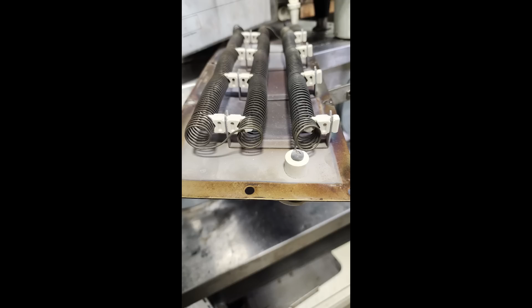This is the old heating element I took out, and over on the left you can see one of the terminals - the ceramic insulator is cracked on one side. This side you're seeing now is good; this little ceramic insulator is the way it should look.